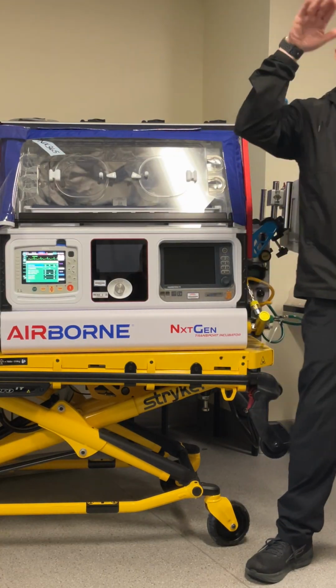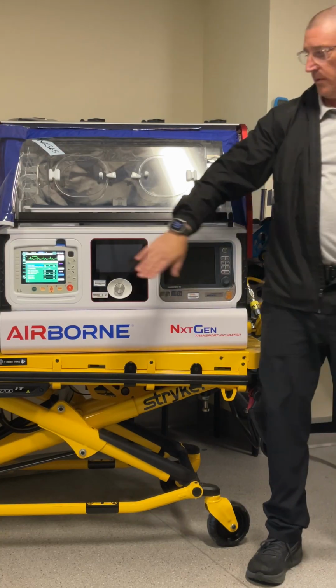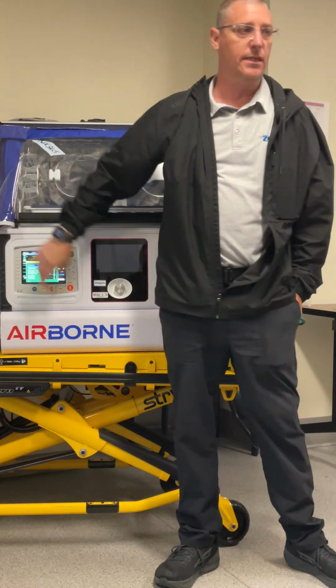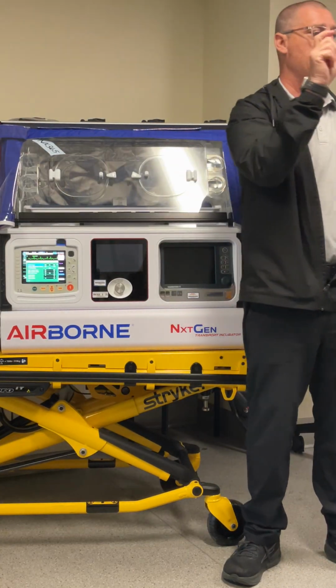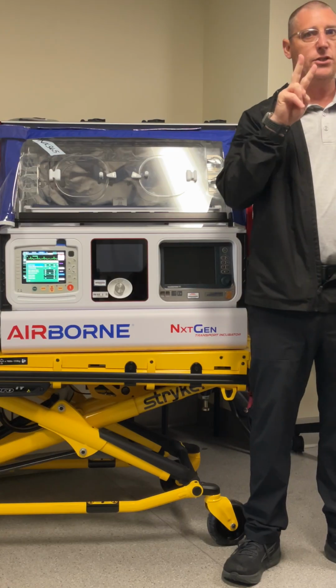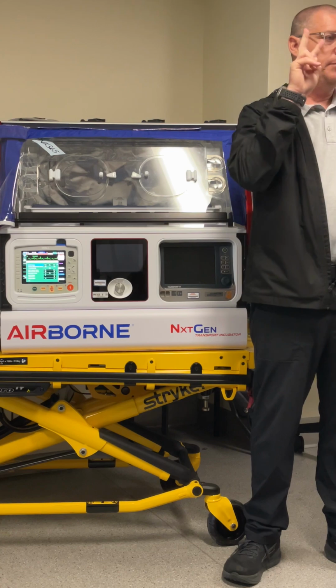If those alarms are going off and you can't get them to clear with that 90 seconds of quiet time, because remember this bell gives me 90 seconds of quiet time, I can go to the bell with the X, hit the bell with the X one time. Up next to your battery symbol, you get a red and white box that has a countdown of, I believe, 4 minutes on that monitor. Yours is 2. I believe we changed your monitor to 2. So you get 2 minutes of quiet time.